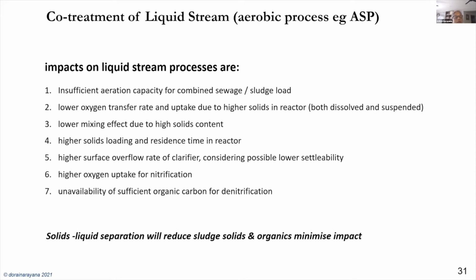And secondly, there could be a lower oxygen transfer rate because of the higher solids in the reactor, both dissolved and suspended, and that could cause the treatment facility to have less efficiency in terms of oxygen transfer. Mixing effect: usually the mixing in the aeration tank could be by mixers or through the aerators itself creating a mixing. And because of the high solids which are in suspension, the mixing effect could be less, right? So this is another thing that is possible.